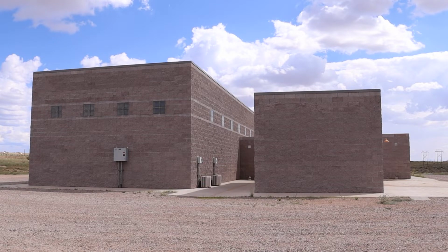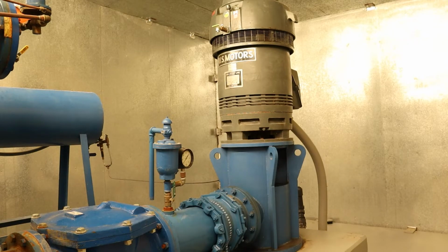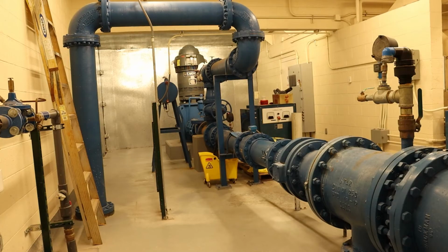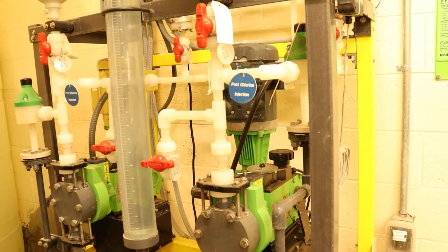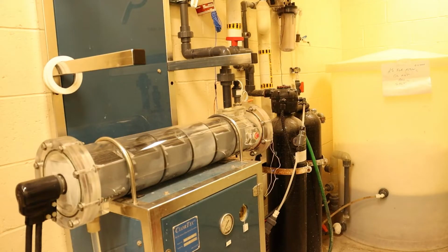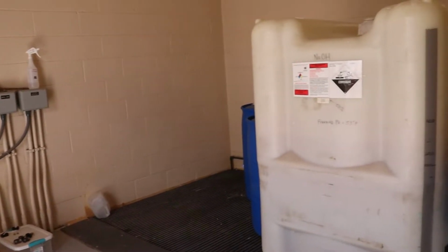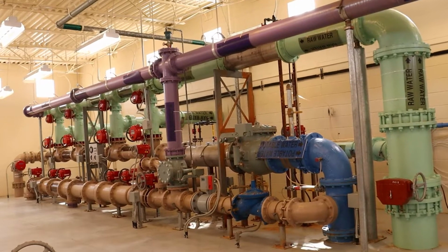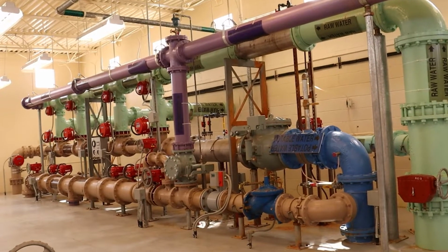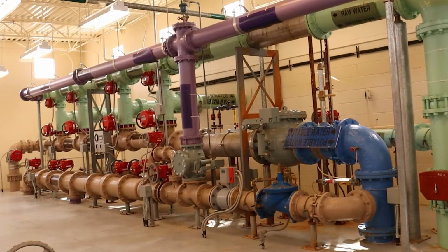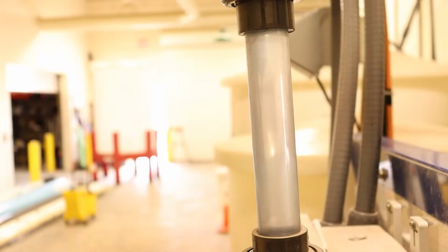The treatment of drinking water begins after pumping the water up from groundwater wells. The water goes through treatment processes such as pH adjustment and filtration to improve quality and taste. The water is then disinfected to ensure that it is free of biological contaminants like bacteria and viruses. A small residual of disinfectant is left in the water for continual disinfection during the distribution and storage of the water. This utility uses an on-site sodium hypochlorite generation system.